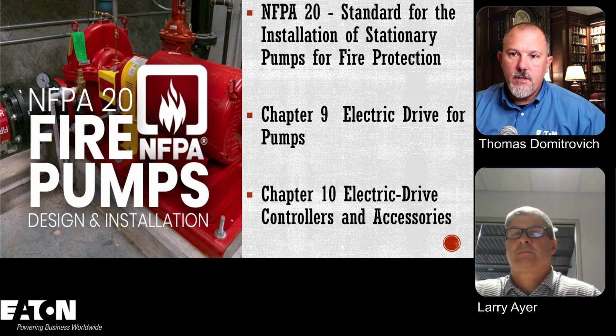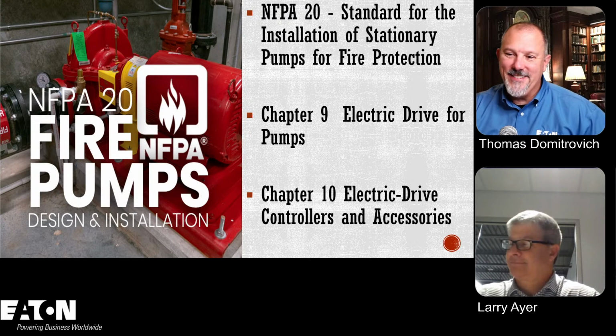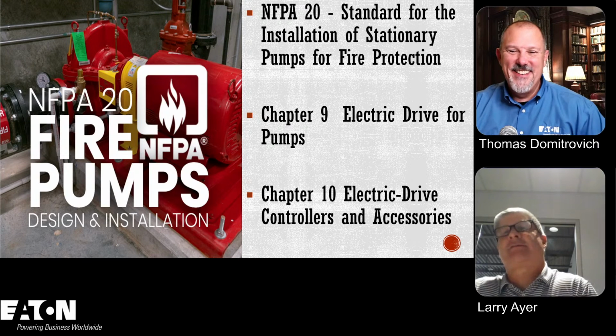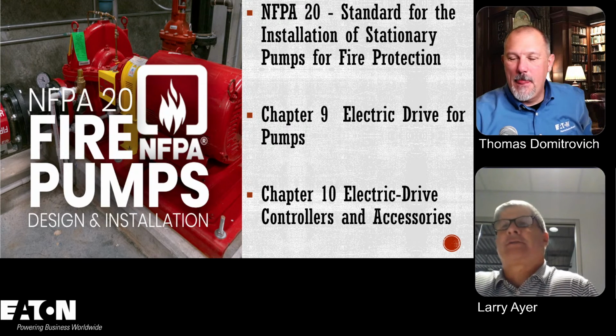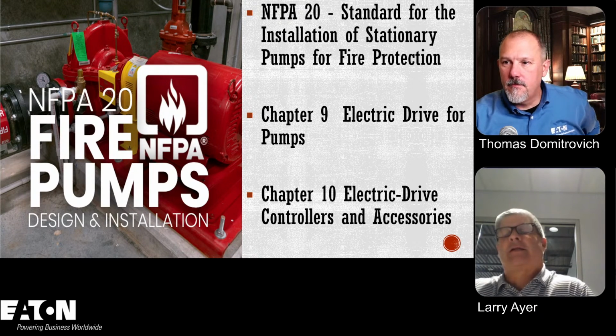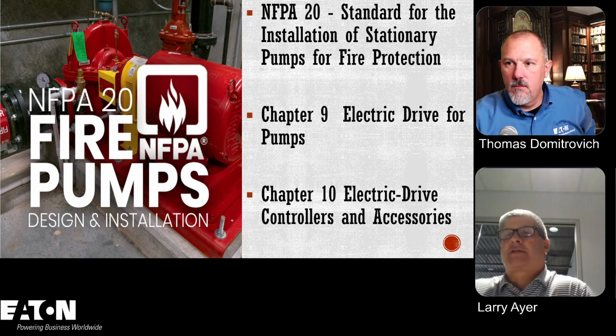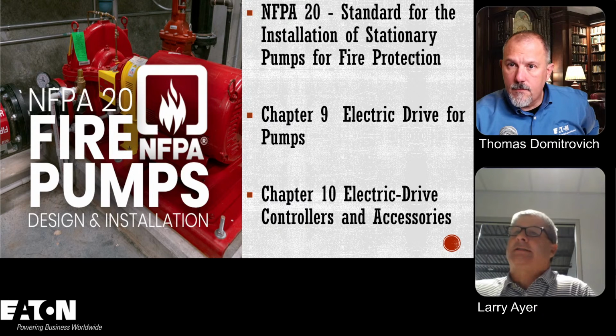There it is, buddy. NFPA 20, the document that you love so well, that you think is so much more organized, right? I do. I think that most of the things you look at in NFPA 20, if you just look at chapters 9 and 10, it really provides a good foundation in an organized fashion of fire pump requirements. You will not find things about protection of feeders, sizing of feeders, and things like that. That's all in 695. But I would encourage people to look at that and get a feel for how it's laid out and what's contained in those two chapters.